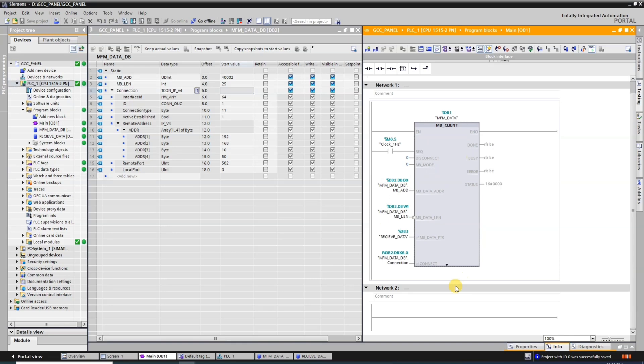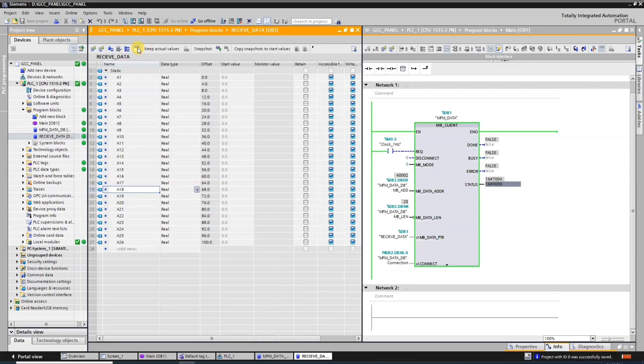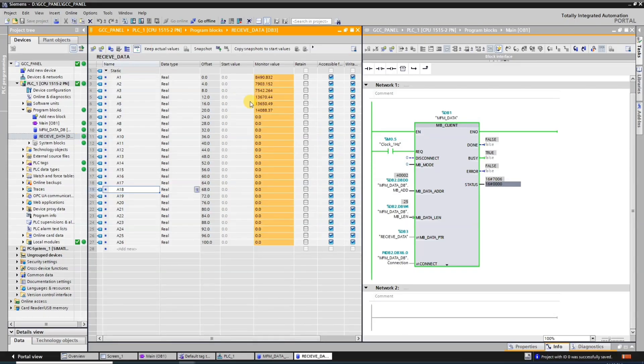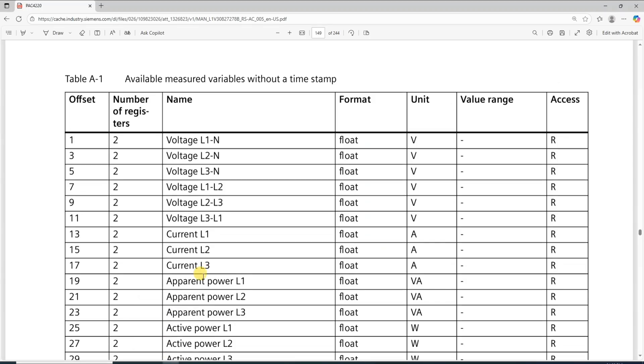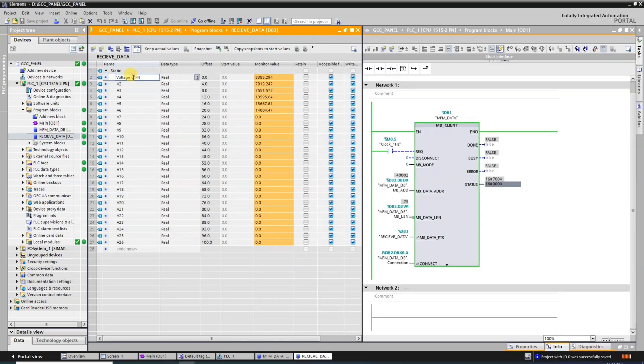Now we check our data. There is a status of 7002, which means our data is being received on our DB. Now go online on your DB so you can check — our data is coming. However, not all data is coming because our data length is set to 25. If you want to read more data, you need to increase the data length so that we receive more data.